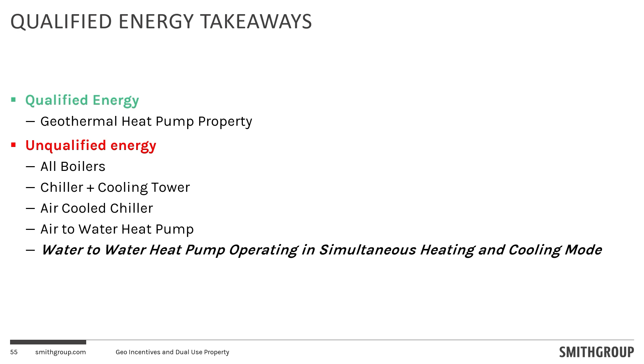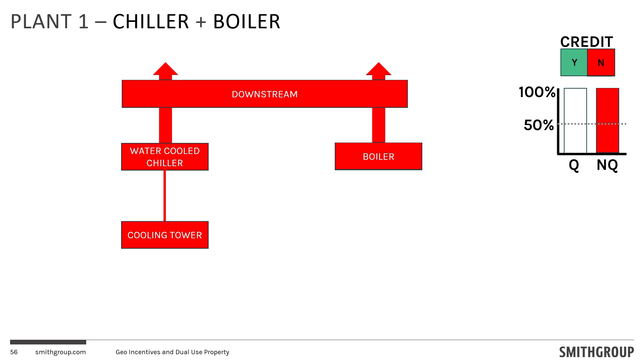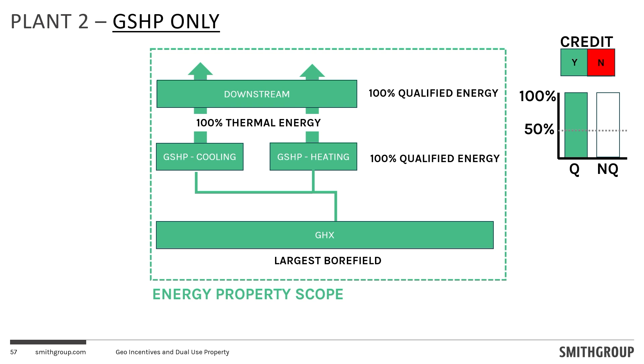So let's get into some examples, here's some schematics. If you had a traditional plant, water-cooled chiller, cooling tower, boiler, that's zero qualifying energy, so nothing gets a credit. Let's say you swap that same building, but you plop in a ground source heat pump. Well, the energy property scope would be the whole scope of that system, the ground heat exchanger, ground source heat pump, and downstream. Everything's qualified, so the downstream gets 100%.